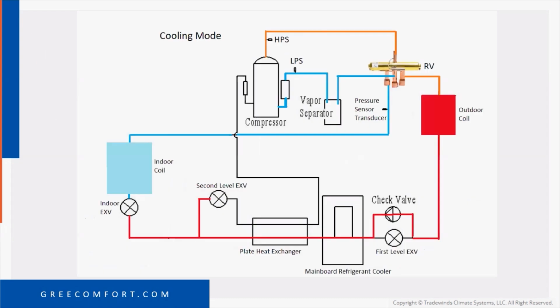Moving on to refrigerant flow, okay? The piping diagram that they have in the service manual, it's wrong. I'm going to get it updated, but they didn't show the plate type heat exchanger. So as you can see right here in this diagram, it does show the plate type heat exchanger. Just so you know, this came to us from GREE. It was all black and white. I just went in and highlighted it to make it a little easier to read with the colors and stuff, okay? And I've always done this, and I'll do it again the same way.